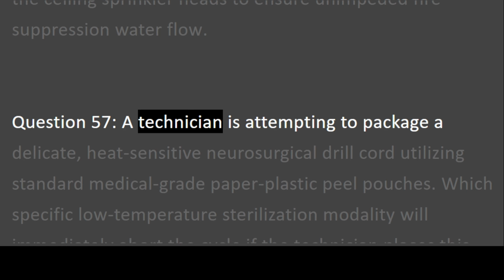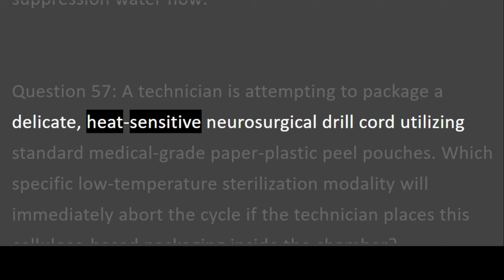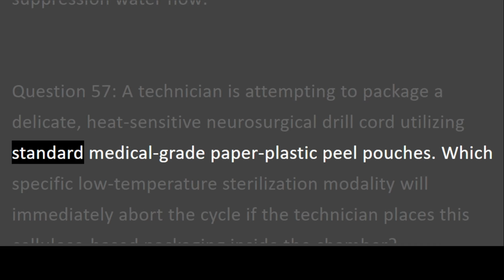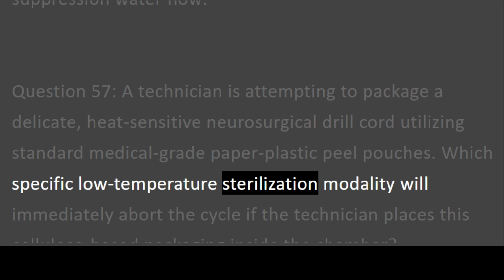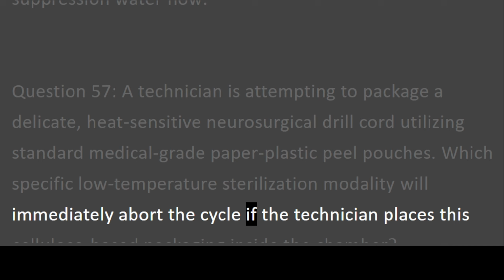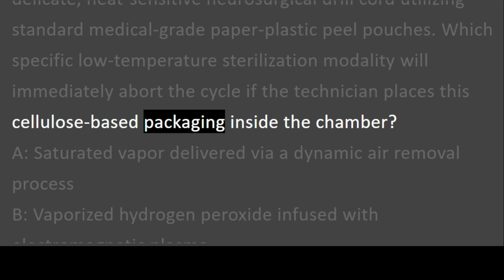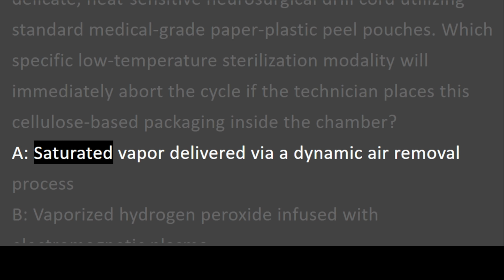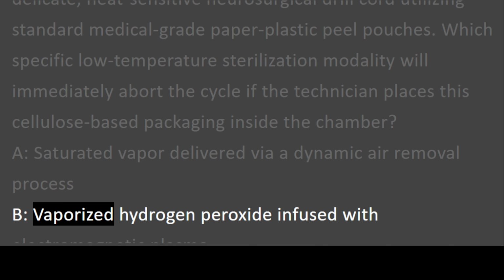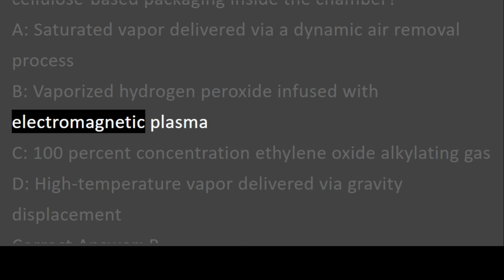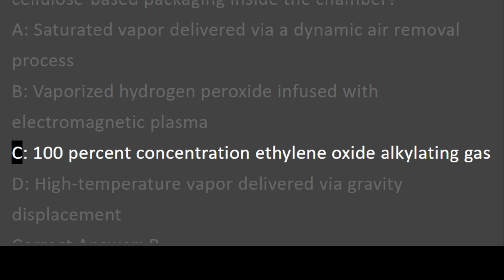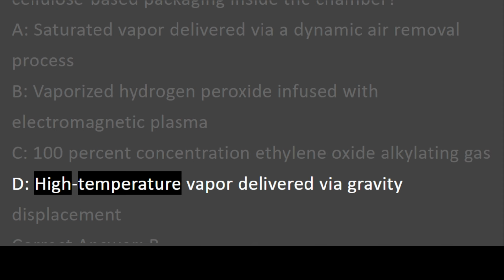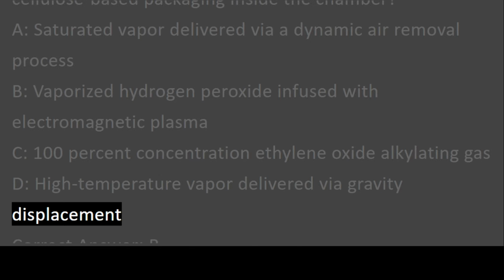Question 57. A technician is attempting to package a delicate, heat-sensitive neurosurgical drill cord utilizing standard medical-grade paper plastic peel pouches. Which specific low-temperature sterilization modality will immediately abort the cycle if the technician places this cellulose-based packaging inside the chamber? A. Saturated vapor delivered via a dynamic air removal process. B. Vaporized hydrogen peroxide infused with electromagnetic plasma. C. 100% concentration ethylene oxide alkylating gas. D. High-temperature vapor delivered via gravity displacement.